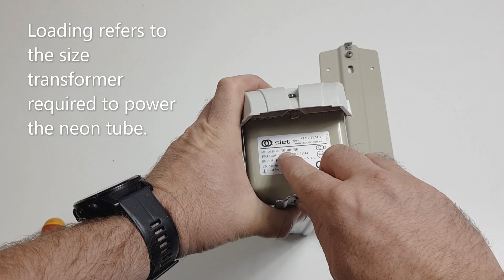These are perfect for that. So with a SIET transformer, or any transformer, you'll be looking for the loading number, which is this one here. This is the voltage, and that's the amperage. So we're looking at this one, it's a 10,000 volt with 30 milliamp. We refer to these as a 1030.